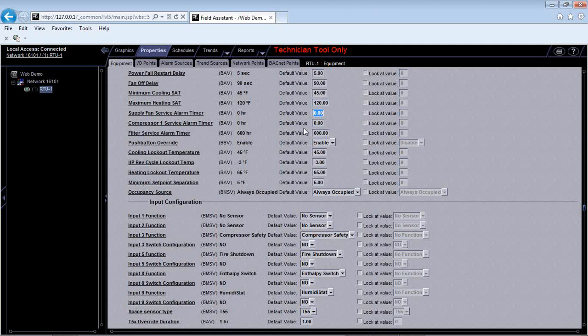This is more if you actually have a Carrier control system set up and you're not tying into a third party, but it's just an option that you can put in there if you want to make your customer aware of maybe they need to look at their service, their supply fan, and maybe change the belt every 600 hours or so. And you have that with the compressor and the filter as well, okay?